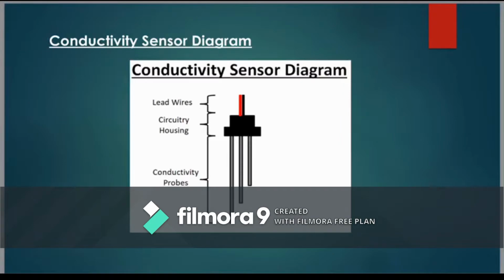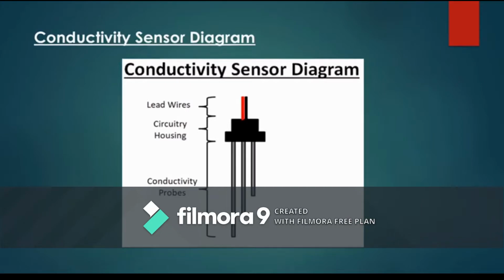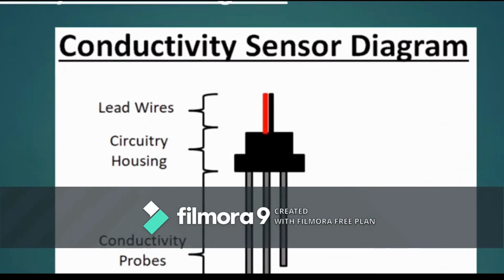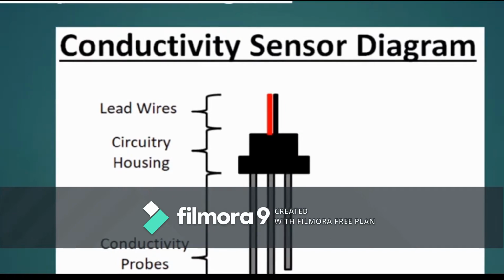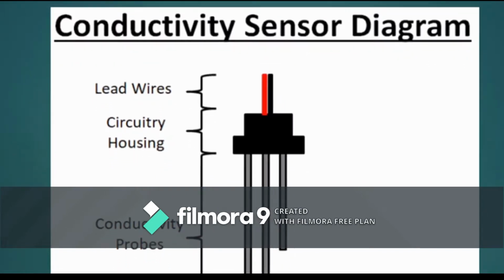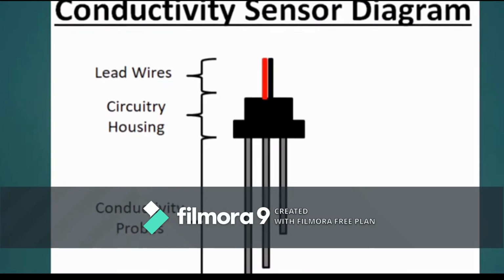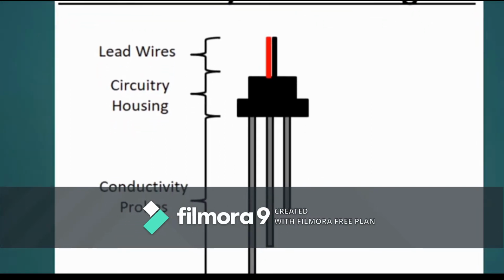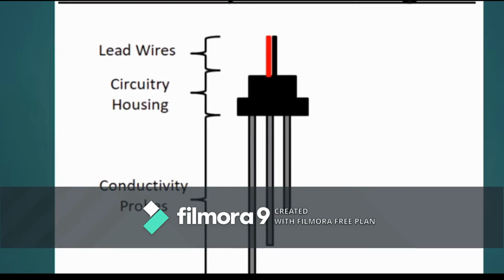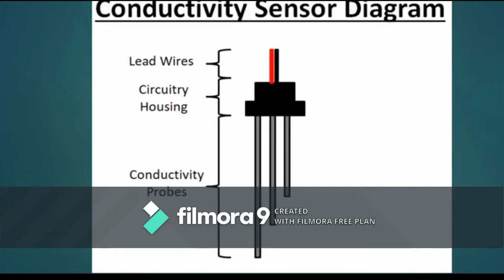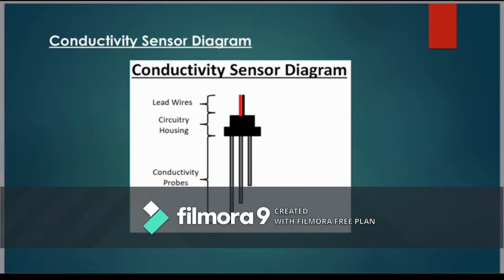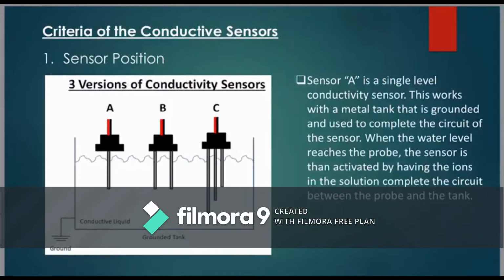So this is the conductivity sensor diagram. So you can see here the red and black is the lead wires section, and below is the circuitry housing, and the last one is the conductivity probes, which is the section that will sense the level of water of the conductive sensor.